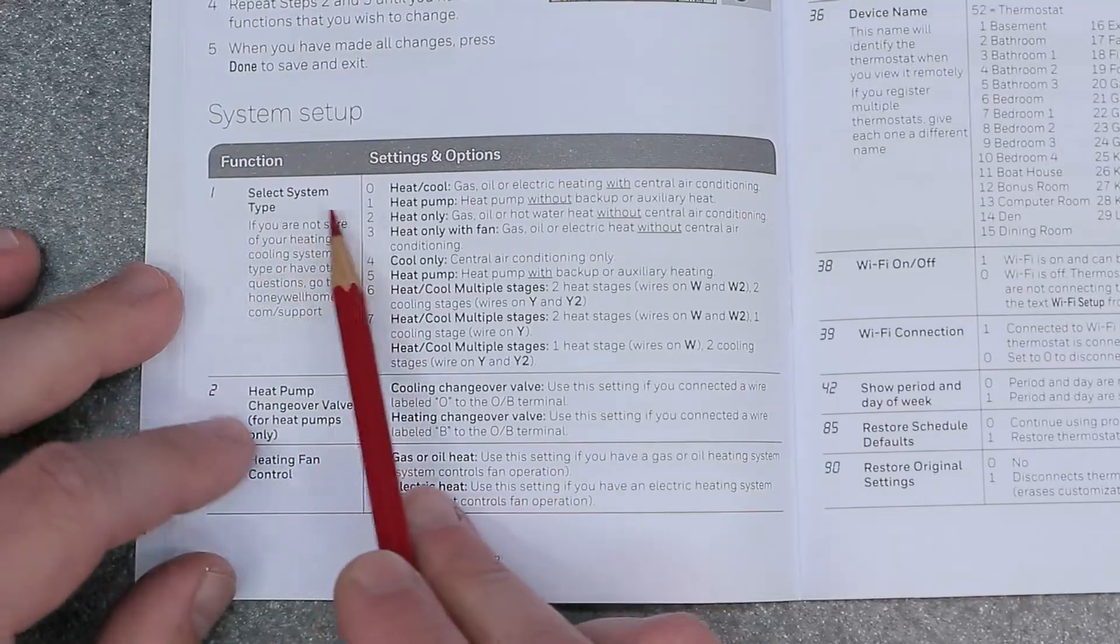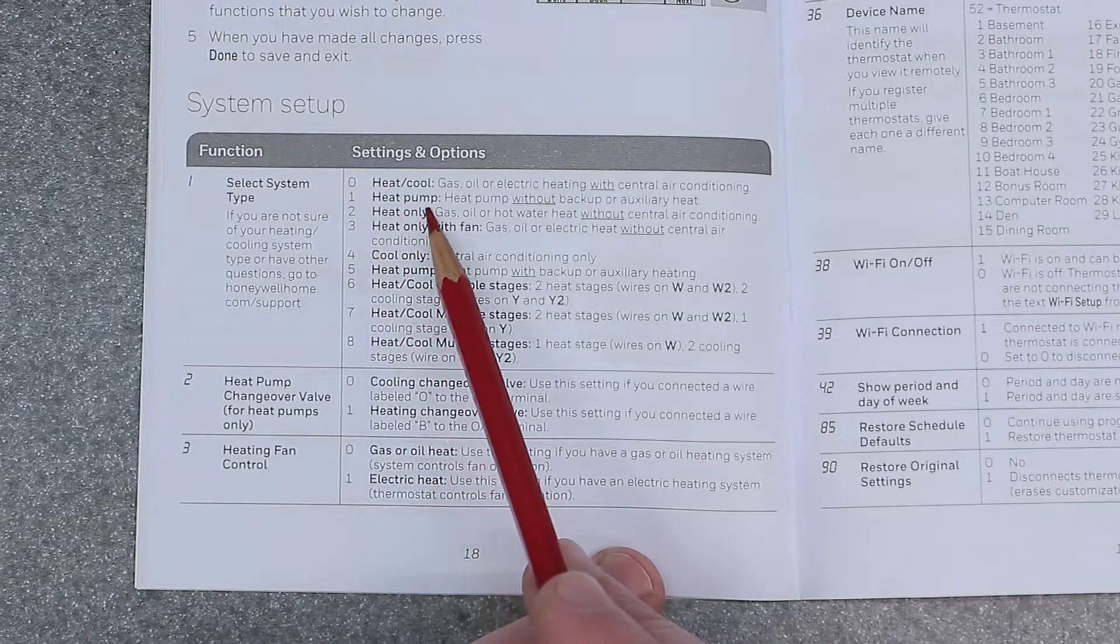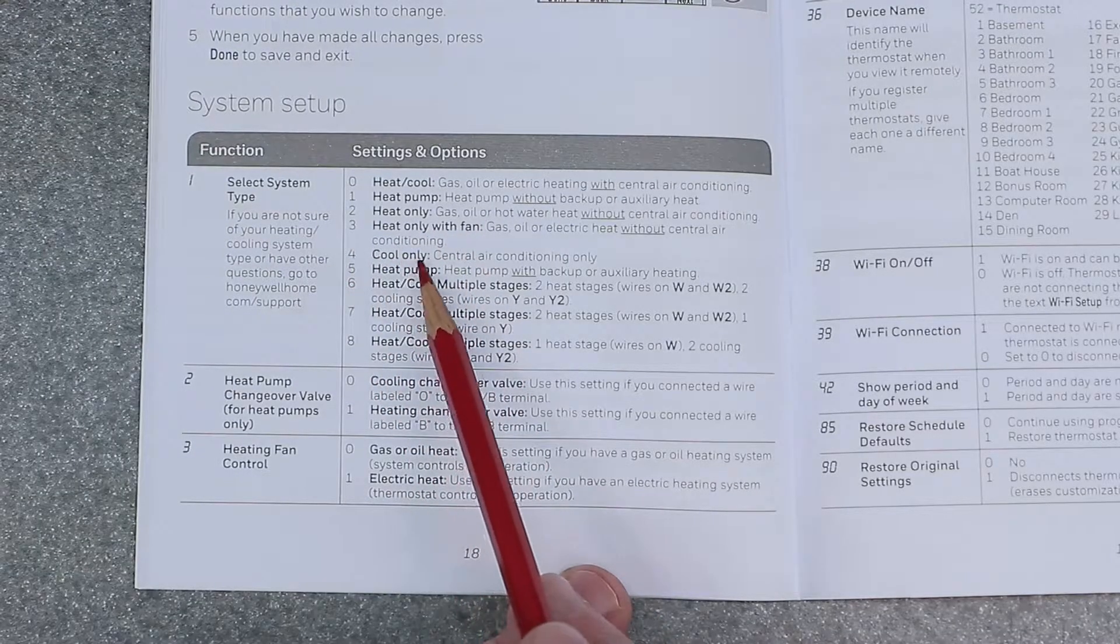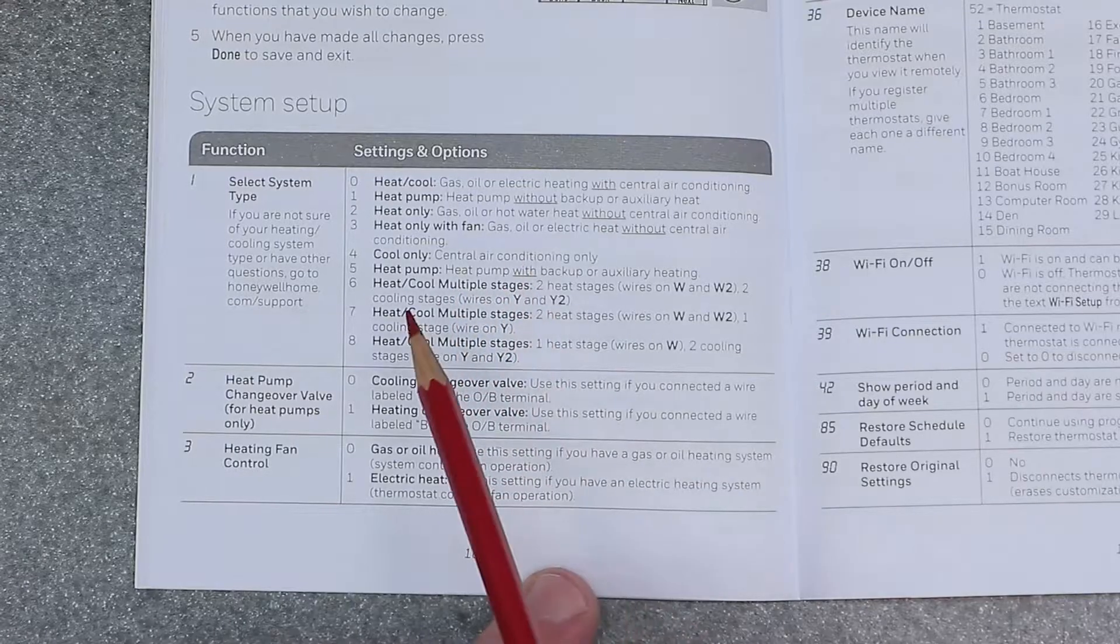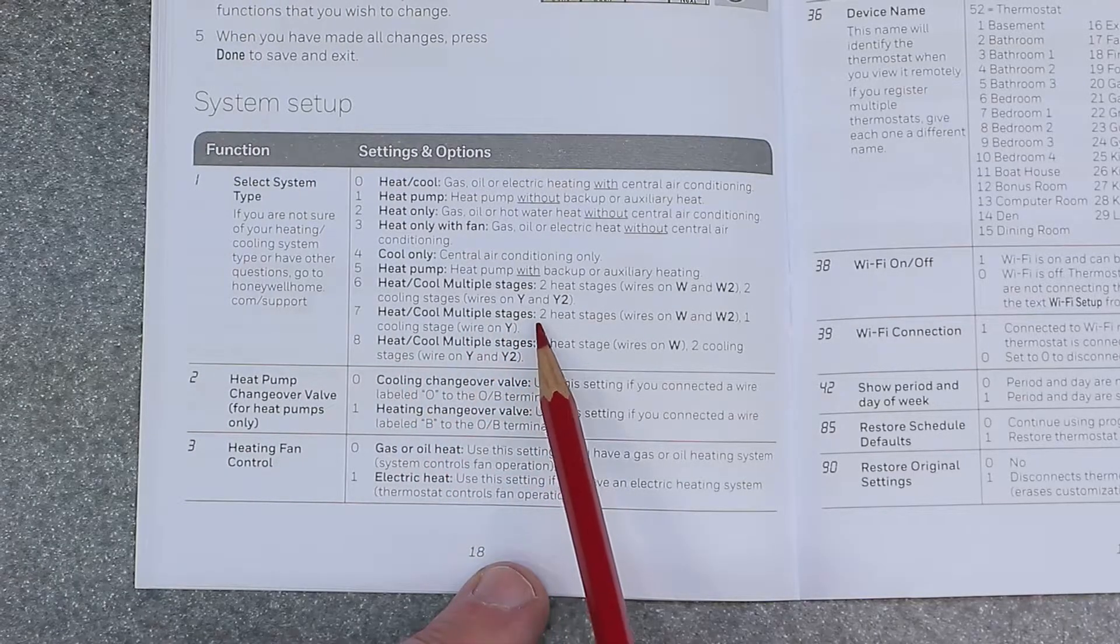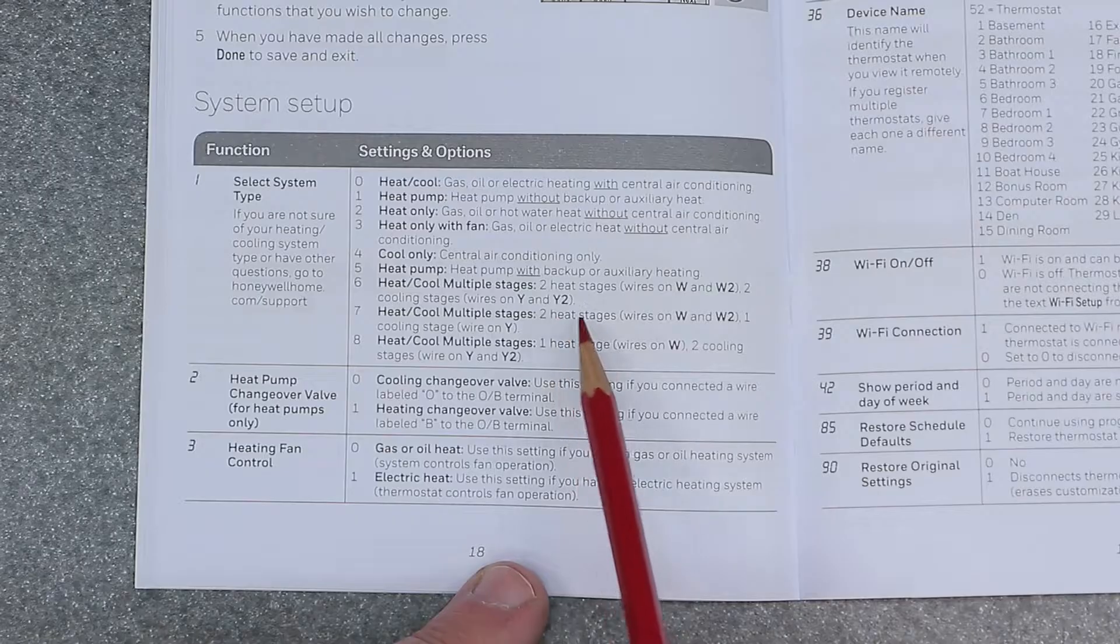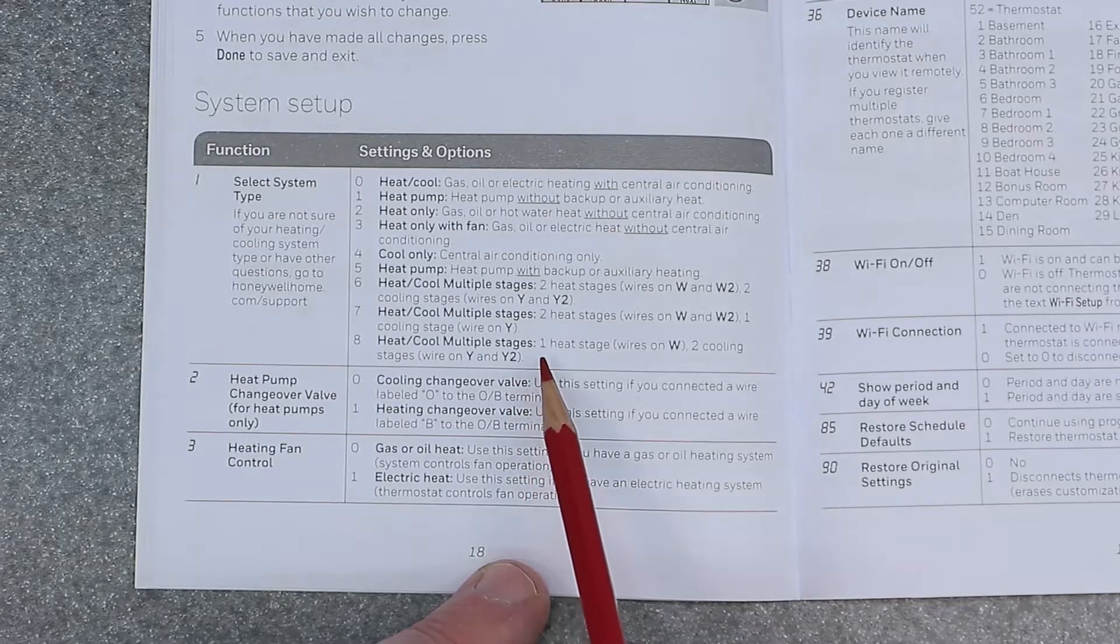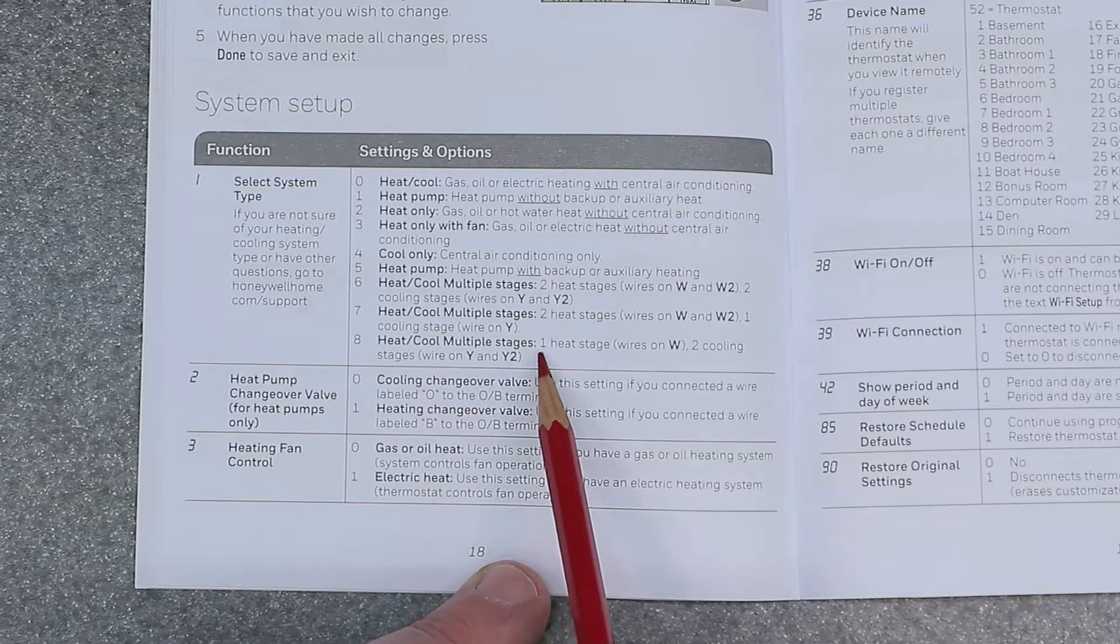So number one is going to be select system type. We have zero equals heat cool. One is heat pump. Two is heat only. Three is heat only with fan. Four is cool only. Five is heat pump. Six is heat cool multiple stages. Seven is heat cool multiple stages. And the difference between here is the way it's wired. So it says two heat stages and two heat stages with different wiring configuration. So I would definitely take a look at this manual if you are setting this up for the first time. But number eight is heat cool multiple stages with one heating stage.